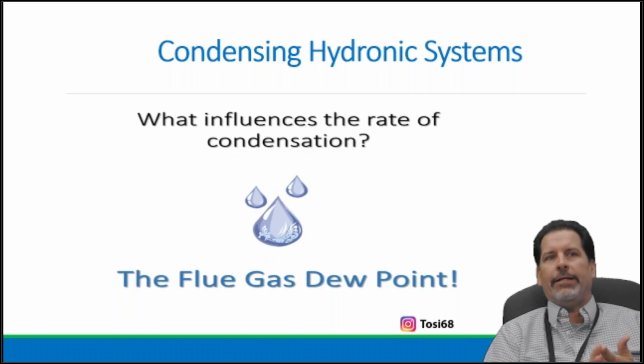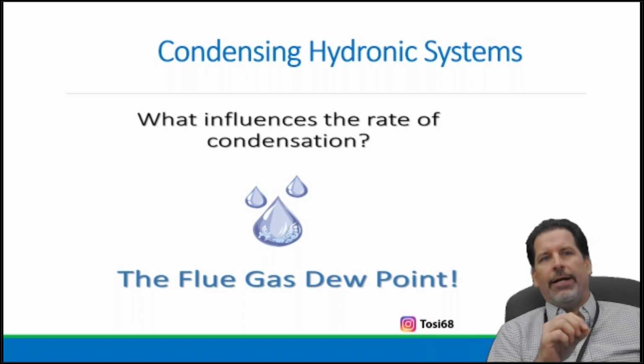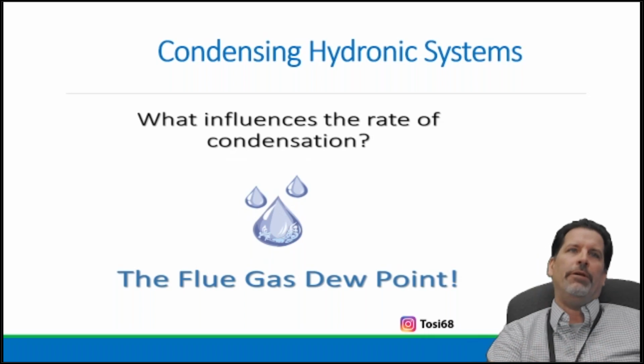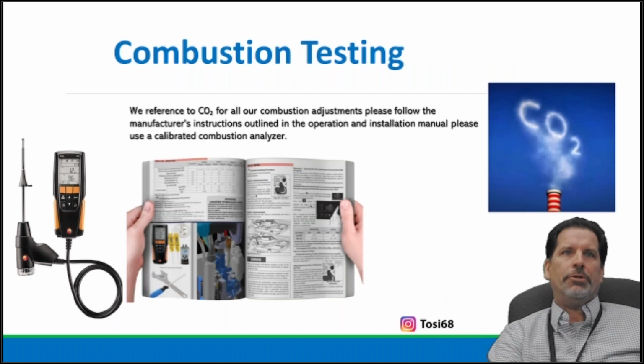Now we're lowering and getting what? Flue gas, right? The dew point, that's what we need to achieve. When we can collapse our flue product, leaving that condensing boiler from a vapor back to a liquid, that's when we achieve high efficiency, right? Read the instructions, right? Every manufacturer gives you the information. We just need to find it and understand it a little better.